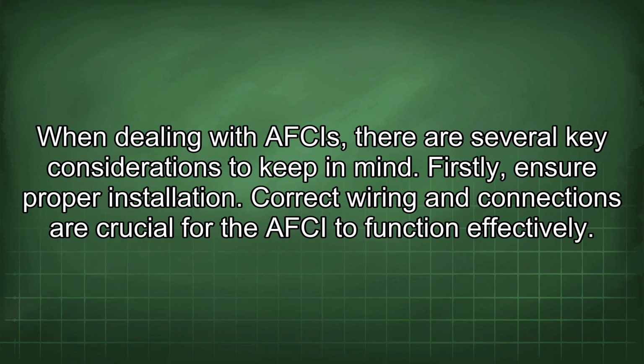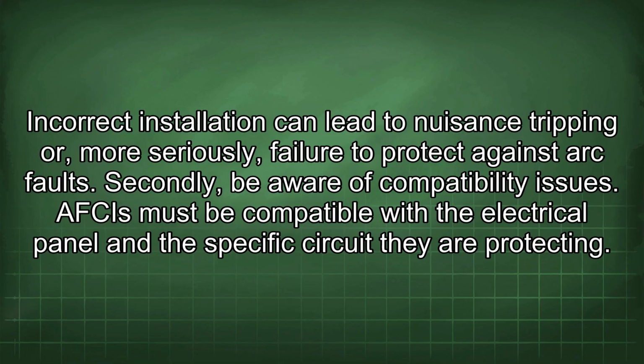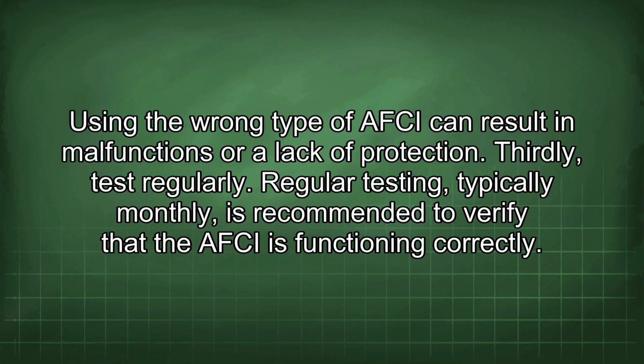When dealing with AFCIs, there are several key considerations to keep in mind. Firstly, ensure proper installation. Correct wiring and connections are crucial for the AFCI to function effectively. Incorrect installation can lead to nuisance tripping or, more seriously, failure to protect against arc faults. Secondly, be aware of compatibility issues. AFCIs must be compatible with the electrical panel and the specific circuit they are protecting. Using the wrong type of AFCI can result in malfunctions or a lack of protection.